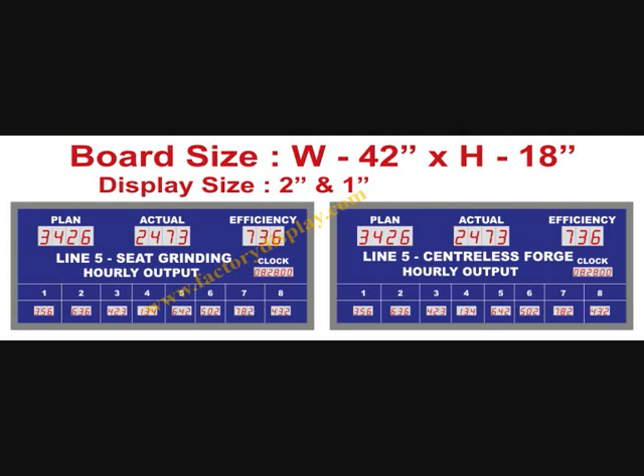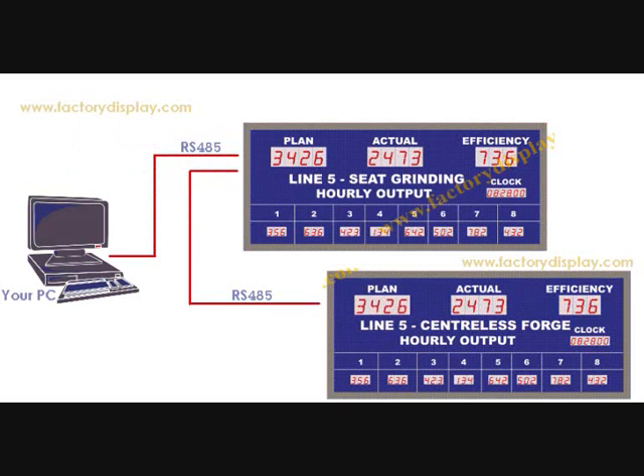Once this is done, the board retains in its memory the settings and then increments the plan based on the cycle time which is programmed. The actual count comes in either as a potential-free contact from your side, or can come as a voltage, or as a digital input from your side. Efficiency is calculated as actual divided by plan, into 100.